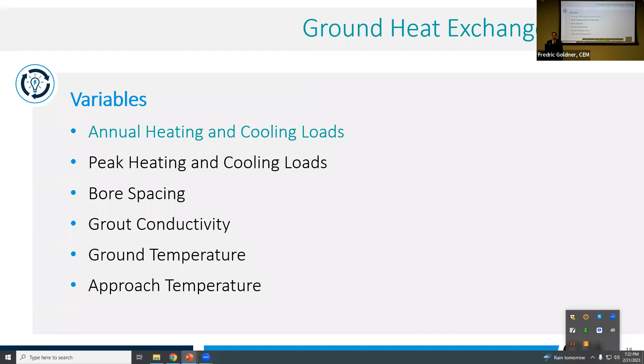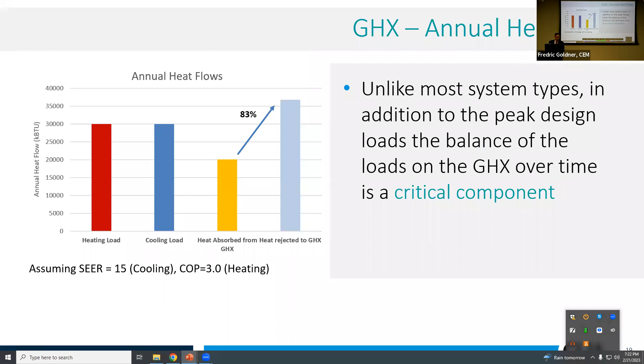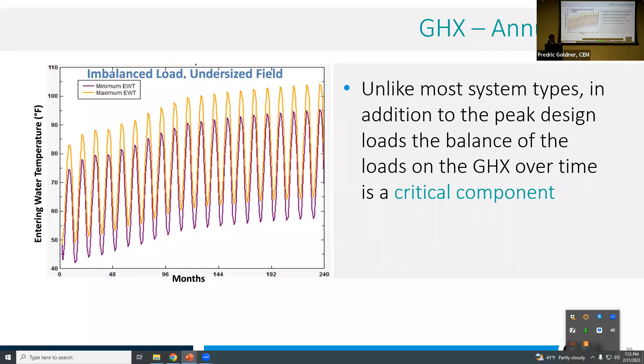Unlike most system types, in addition to peak design loads, the balance of the loads on the GHX over time is a critical component. I'm seeing, in 15 years, my Earth is gaining 3 degrees of temperature. We don't want to find ourselves having to deal with a warming Earth. Undersized systems, unlike most system types, in addition to the peak design loads, the balance of the loads on the GHX over time is a critical component. So what we're showing here is maximum and minimum water temperatures. You can see that this loop, it's hot. This heat exchanger is hot because over time, 20 years, pretty soon my Earth was now like 105 degrees. And here's where we started. So no bueno.